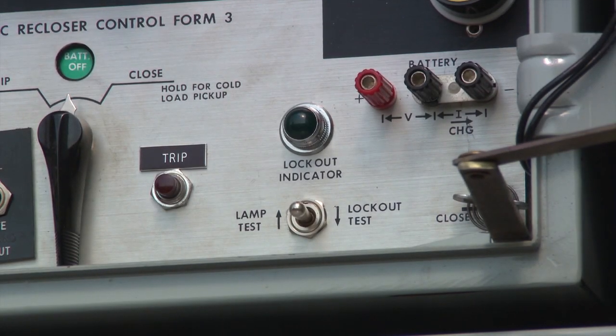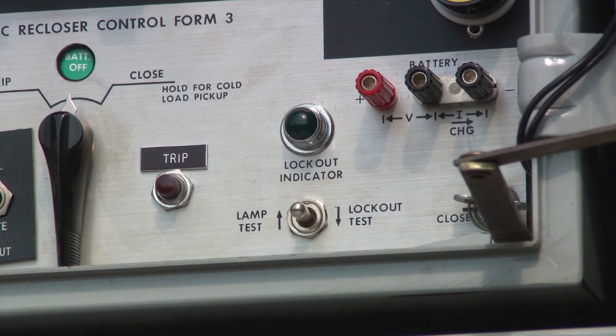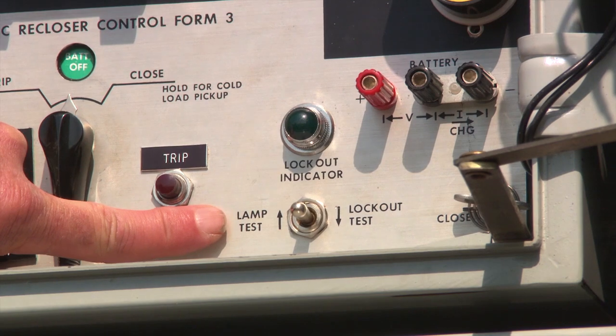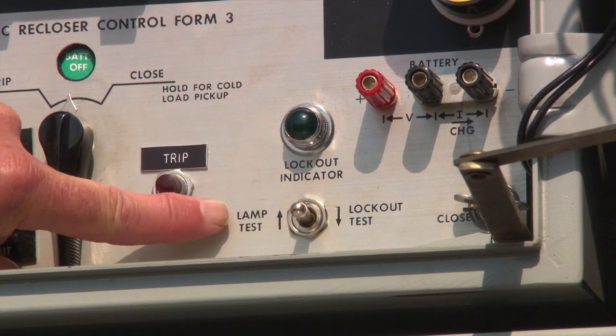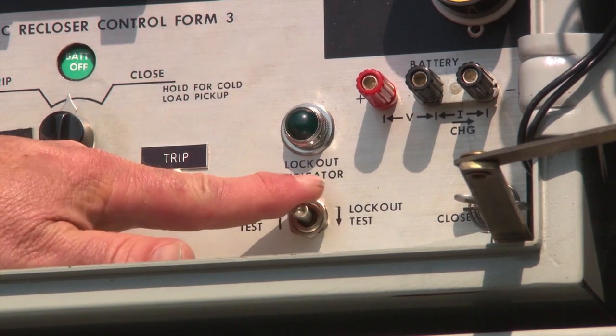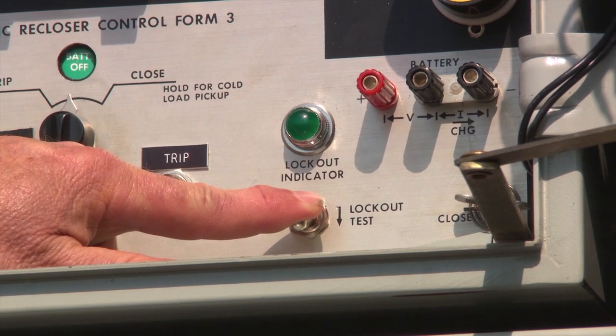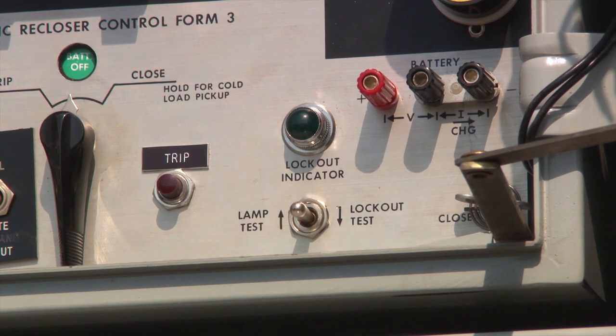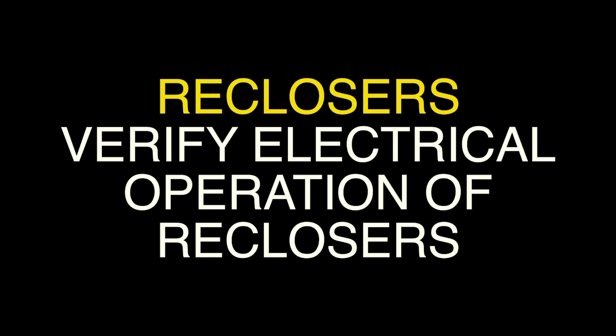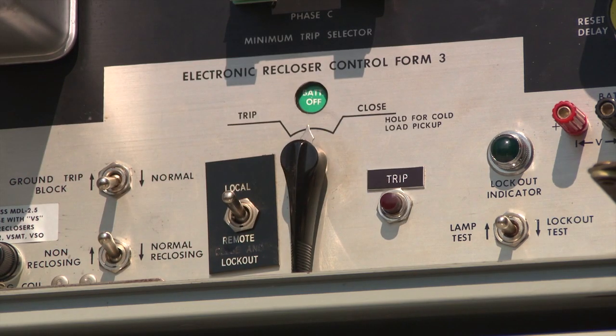Using the lamp test and lockout test switch, verify the green lockout test light illuminates. The lockout indicator signal lamp provides visual indication of lockout when the switch is operated. The lamp test lockout indicating switch indicates lockout and tests the indicating lamp. Verify electrical operation of the reclosers.